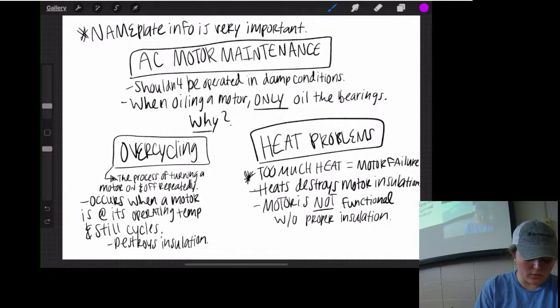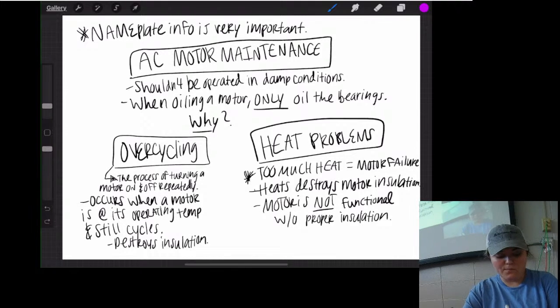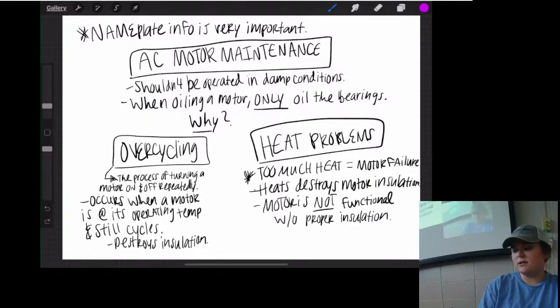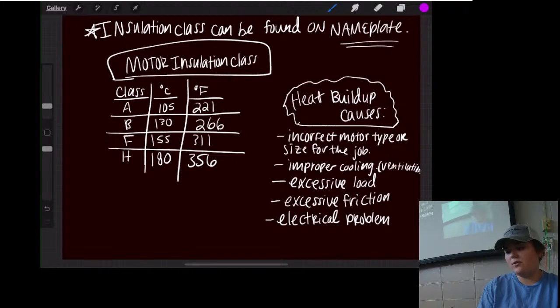Because heat destroys motor insulation, that causes short circuits with the windings. The life of motor insulation is shortened as the heat in a motor increases beyond the temperature rating of the insulation. So the higher the temperature, the sooner the insulation fails, and this temperature rating of motor insulation is listed as the insulation class. The insulation class can be found on the nameplate — the holy grail, right?